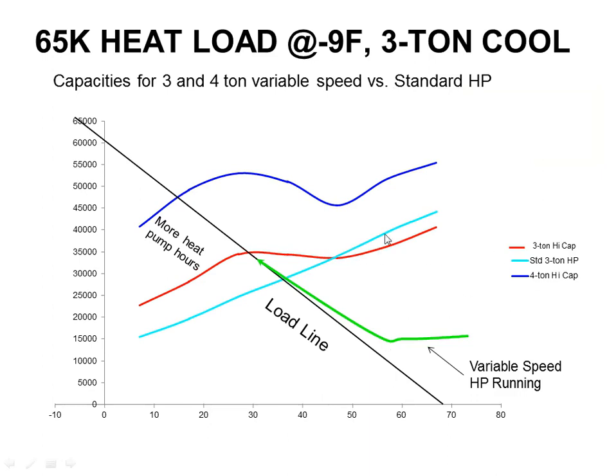However, if I upsize it, or if I heating size it, more for the 4 ton heat pump, it becomes this dark blue line. If I follow that guy along, when I get over to, we'll call it 16, 17 degrees outside, that's when I can no longer make enough heat. So that's a pretty big difference between 35 and 17. That's a couple thousand hours of runtime. So that's kind of where the advantage of this guy is going to fall into play, is being able to upsize him.